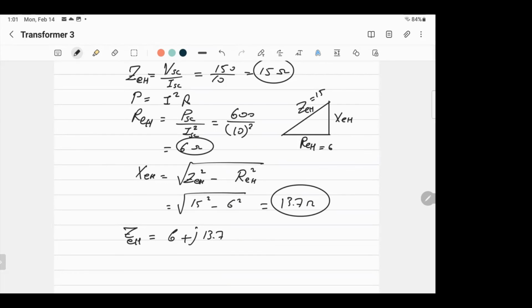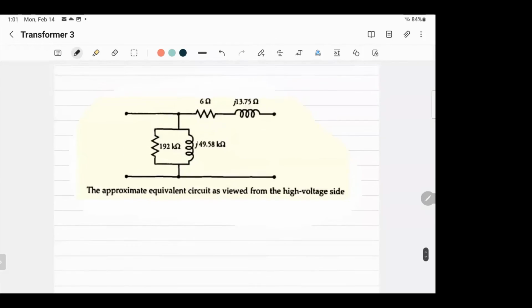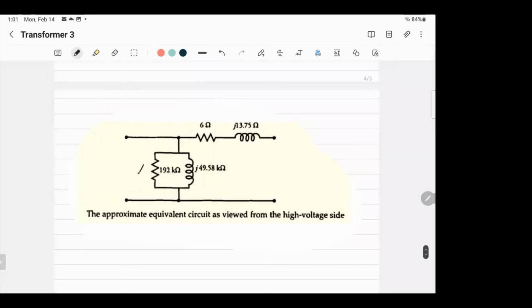Now you can get anything, because here's the equivalent circuit — that's RC, that's XM, all referred to one side, and that's the resistance and inductance. But you have to refer everything to the high voltage side, so I transformed R and X to the high voltage side using A squared, since they were measured at the low voltage side. The short circuit values, 6 and 13.75, were already in the high voltage side, so no transformation was needed there.